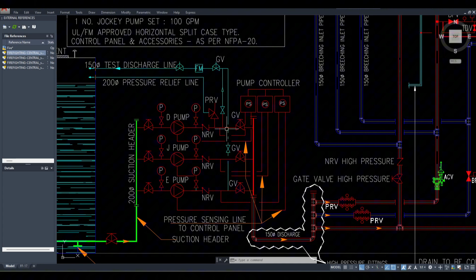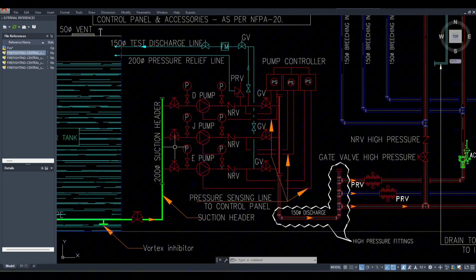So this is one example: suppose they have made a connection where the pump is here and they connected it directly without an isolation valve. You can quickly give the comment, please provide the isolation valve in all the lines. Or if they have kept the header very close to the pump, you can say please provide 1.2 meter distance from this pump.